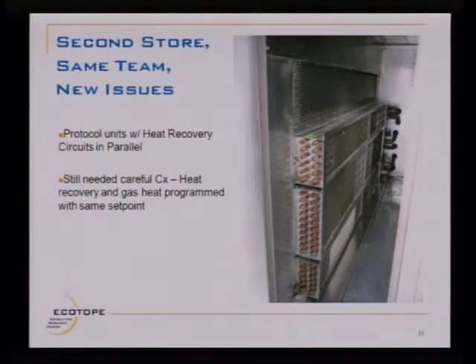Notice that there's 3 coils in parallel, and then up at the top there's a big bypass section. So 25% of the air is bypassing the coils at all times. I could never get a good answer from the designers why they did this. It almost guarantees that the natural gas will have to come on because the air won't be warm enough. Having them all in parallel means that if only one of the systems is running at much capacity at a time, then most of the air going through the air handler is not even flowing over a hot coil.